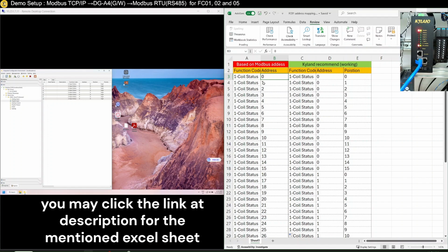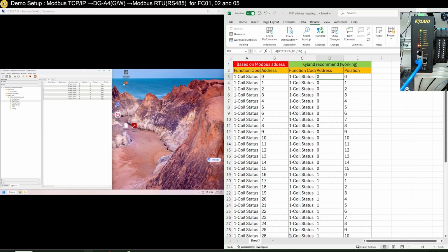So instead of putting the actual address, it comes with a multiplier of 16 followed by the remainder here. So for example, let's say I want to start from address 1000. Notice instead of putting 1000, you have to put the address 62. How do I arrive at this 62? I divide by 16, and the remainder will be put here, which is 8. So let me increment this.